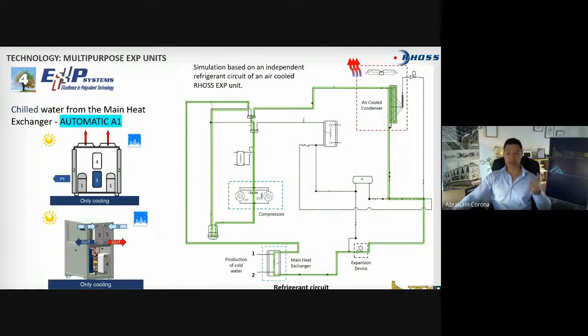Look at the main heat exchanger, that in this case becomes the main evaporator. We have 1 or 2 pipes. The unit is working only as a 2-pipe system automatically. It's generating cool water, maybe from 12 to 7. Inside that heat exchanger, the refrigerant is getting to vapor, to gas, going all the way through the 4-way valve, going to the compressor. We're going to the condenser after. We reject the heat. We're getting heat from the water and, through the work of the compressor, of course, rejecting it to the environment. We go back to the expansion device and we repeat the cycle. Basically, the unit by itself has decided to run as a chiller. It has decided to run as a 2-pipe system.